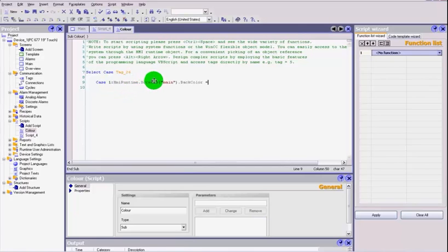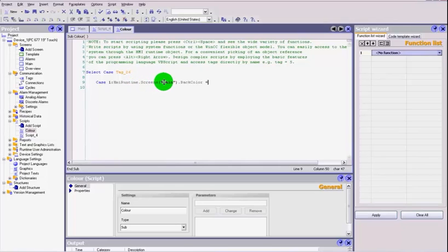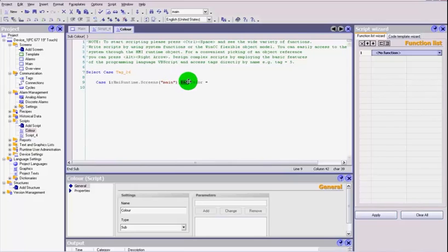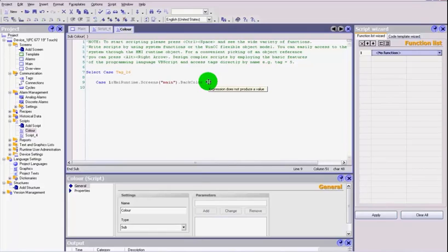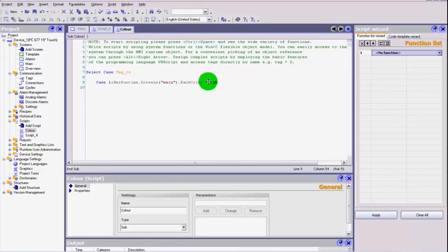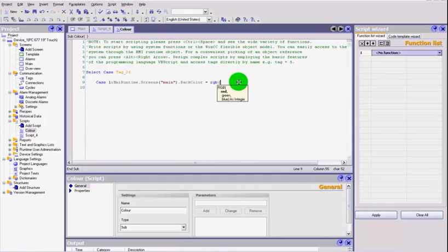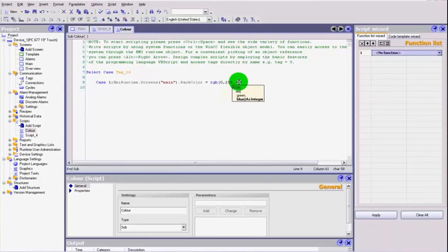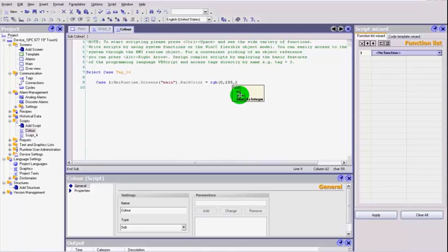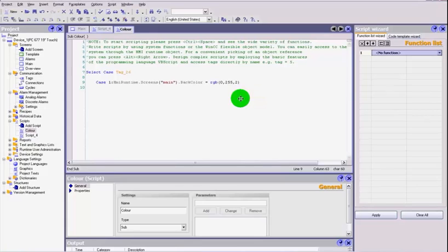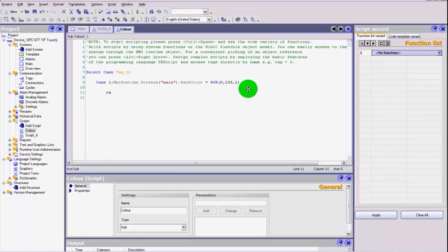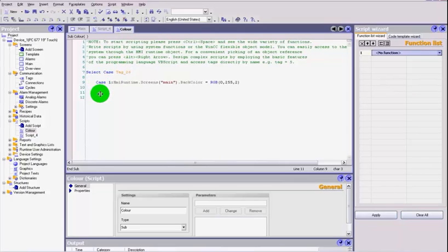Then dot again and we select back color. So our object is HMI runtime dot screens, select the screen that you want to change, dot back color. That is the object part that we want to change. Equal to, now we do it in the RGB. Then by opening your brackets you will notice that you now get three values: red, green, blue, and they've got to be as integers. I think green was something like 0, 255, 2. So I'm putting in the value of red as zero, full 255 green, and I'm adding a little bit of blue. We close that down, close the brackets down.